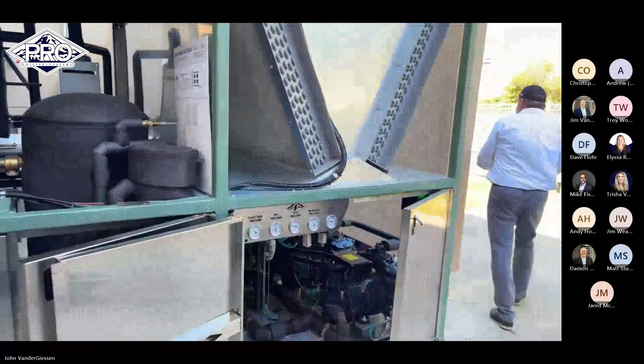What you may or may not have noticed is we have kW meters on both machines, so we'll be monitoring the actual amount of power each unit is using independently. We also have remote monitoring on both systems, so we see exactly how much runtime the compressors are operating, and we'll be able to get a really great side-by-side efficiency comparison.